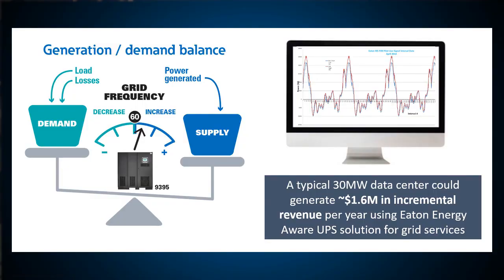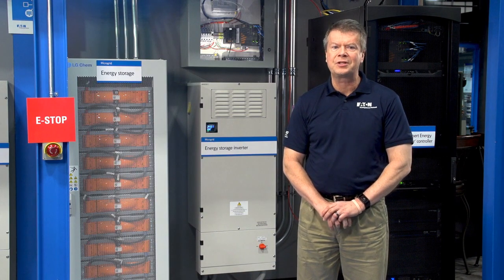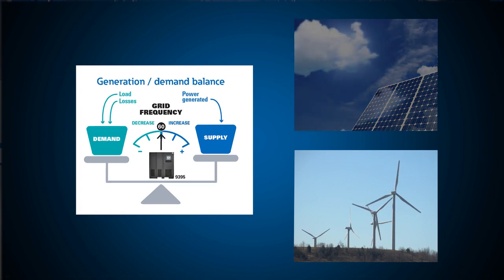By tying the UPS to the utility signal, the utility company tells the UPS to either consume or export energy in response to frequency changes on the grid. This action is contributing to the decarbonization of the grid by permitting a higher percentage of renewable energy sources to be installed, since the UPS is smoothing the erratic power produced by these sources, which happens when a cloud passes over or the wind stops blowing.